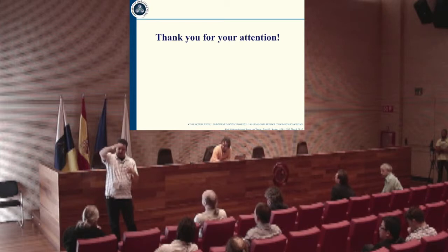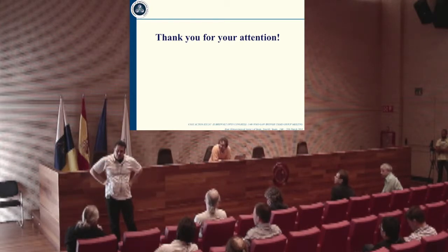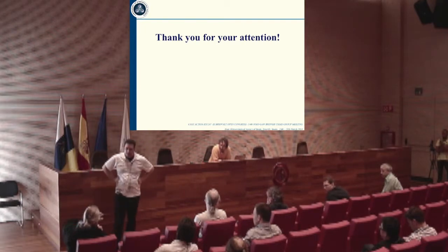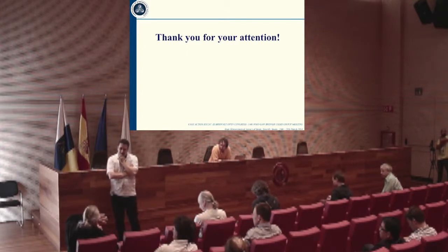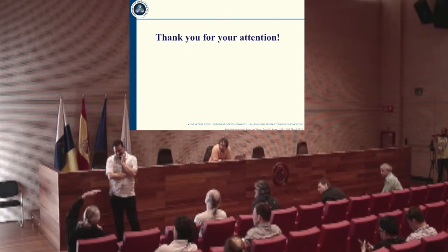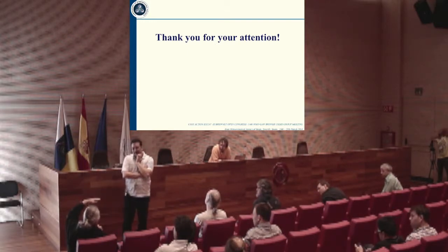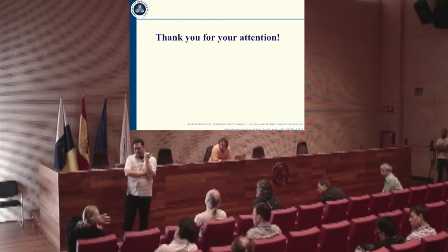There are two comments about that. One is the question of whether you're filling the field of view of the instrument uniformly in all positions. My suspicion would be that the diffuser might give a different answer than the direct views if there's an issue about filling the field.